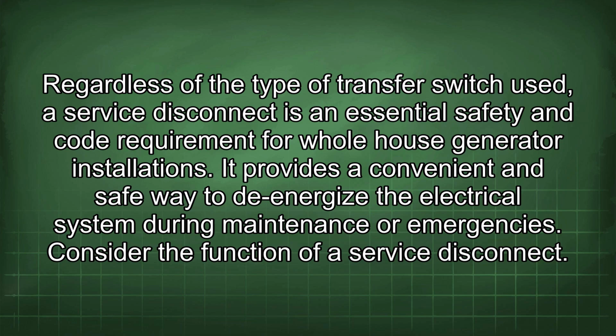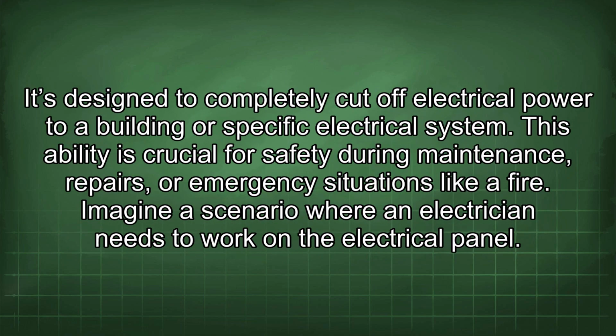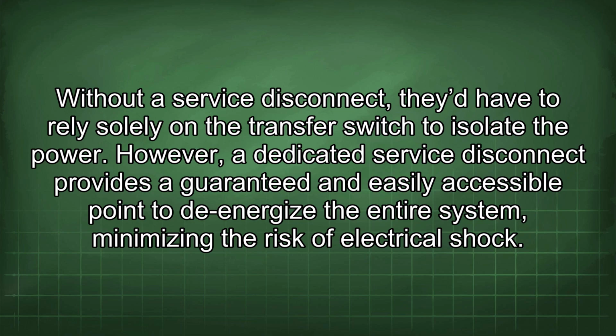Consider the function of a service disconnect. It's designed to completely cut off electrical power to a building or specific electrical system. This ability is crucial for safety during maintenance, repairs, or emergency situations like a fire. Imagine a scenario where an electrician needs to work on the electrical panel. Without a service disconnect, they'd have to rely solely on the transfer switch to isolate the power.